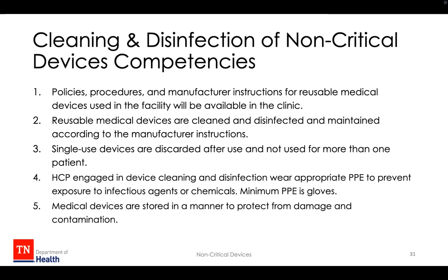Here are some of the competencies for cleaning and disinfection of non-critical devices. Policies, procedures, and manufacturer's instructions are used in the facility and available. Reusable medical devices are cleaned, disinfected, and maintained according to the manufacturer's instructions. Single-use devices are discarded after use and not used for more than one patient. Healthcare workers who are doing the cleaning and disinfection wear the appropriate PPE, at a minimum gloves, and medical devices are stored in a manner to protect from damage and contamination.